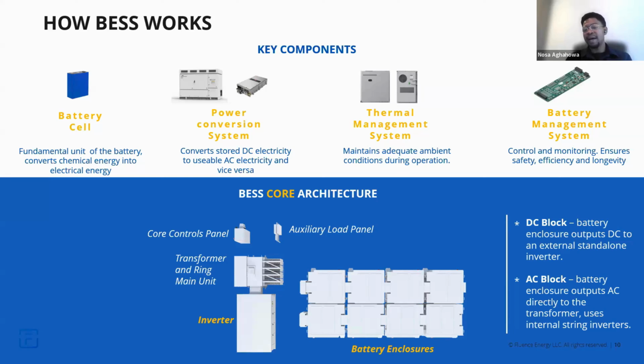When the battery is idle, being charged, or discharged, the thermal system ensures the average temperature of the battery cell is kept at a sweet spot of around 20 degrees Celsius. If it's too high or too low, the battery will perform inefficiently, and this can also compromise the expected life of the battery cells.